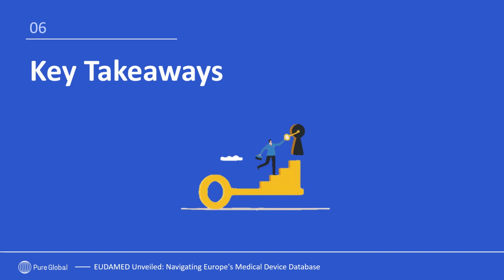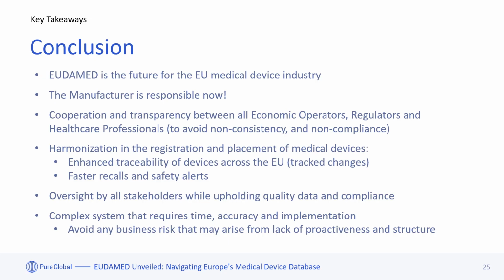To conclude, let's summarize the key takeaways from this presentation on navigating EUDAMED. EUDAMED is the future for the EU medical device industry. Every manufacturer is responsible for its own data and compliance. Manufacturers are now responsible for the device registration, unlike in the past, where maybe the EUAR used to do it for you in the national databases or other economic operators.